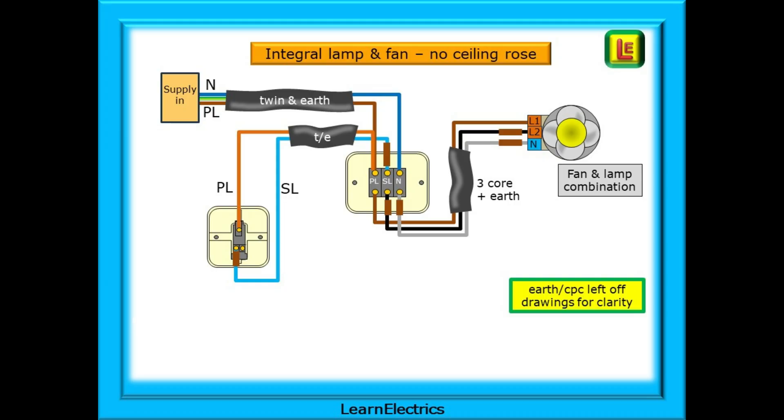And this is how they were wired. Direct to the isolator switch. Looking at it you can see that it has the same connections as a three plate ceiling rose. In this case twin and earth cable went from the consumer unit to the isolator and also from the isolator to the light switch. Three core plus earth strapper cable was used from the isolator to the fan and lamp combination. Easy when you've seen it done.